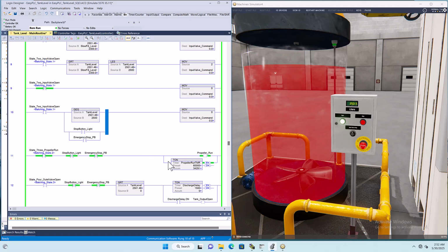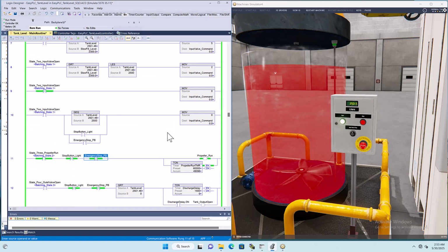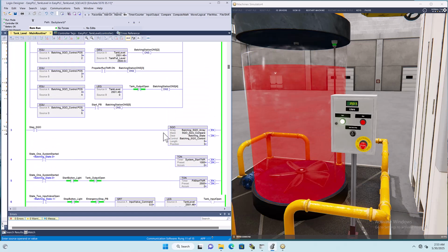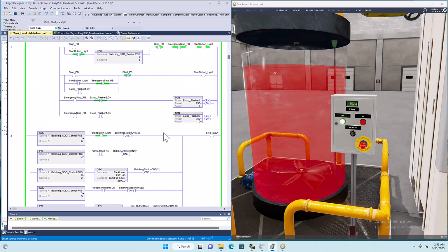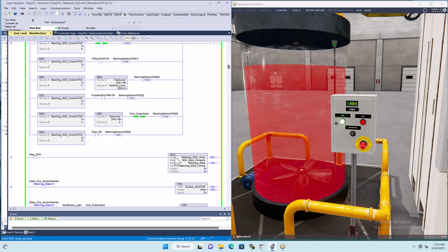If that time were extended to 10 or 15 minutes, then you would put in a retentive timer, and you could put in a reset on the very next step. But for the sake of argument, the system is fully functional the way it is, and this is the simple way to have a simple recovery for your SQO, or your sequencer.